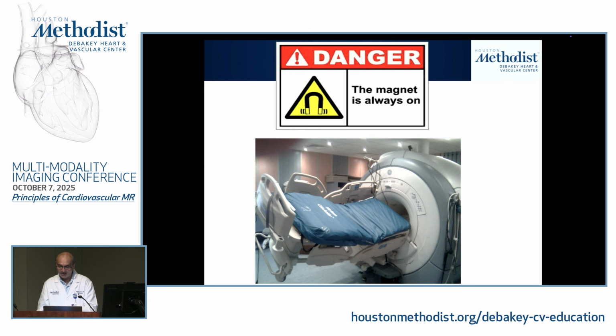This is an example, not from here, where somebody thought, it's probably after hours and they're cleaning up, let me move this bed. What happens is a metallic object that's ferromagnetic will get pulled to the magnetic field. And the magnetic field, as you get closer and closer to it, gets exponentially stronger. So it can take an entire bed like this and just pull it in, all right?